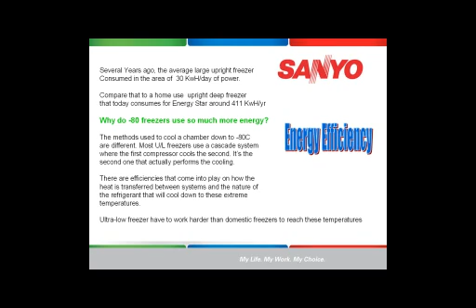The challenge is to maintain performance while reducing energy consumption. When you put product in these freezers, you want to make sure that they're stored at that temperature for years, not having any problems, and that the heat energy that's in those products is withdrawn very quickly. The easiest method to do that as it relates to energy efficiency is to reduce the size of the refrigeration system and put in smaller compressors. The problem is that you need to maintain the heat removal to maintain your critical sample's integrity. So the solution that we're all challenged with is to increase the efficiency of the system without sacrificing capacity.